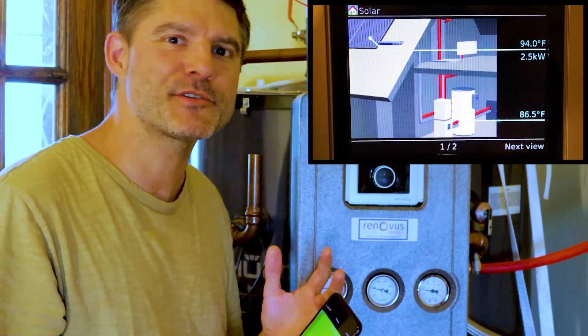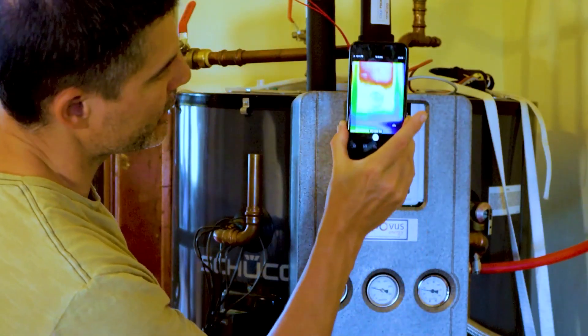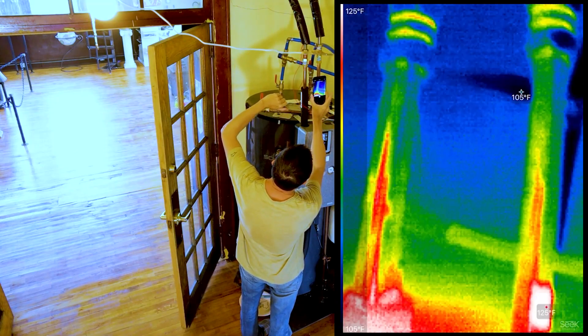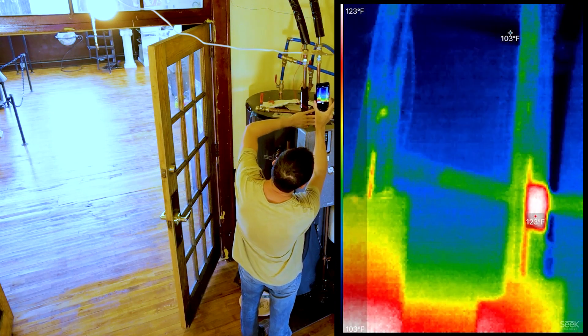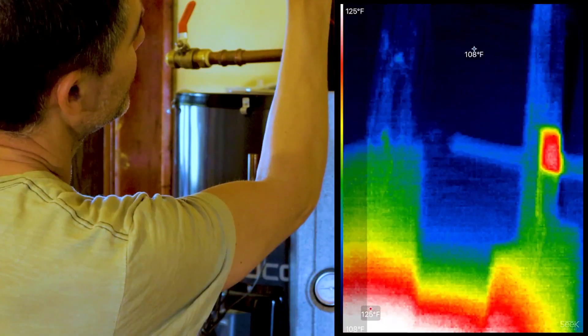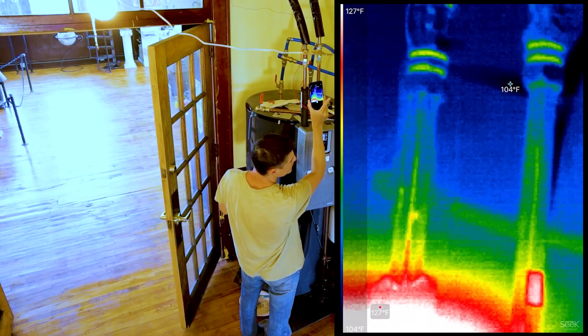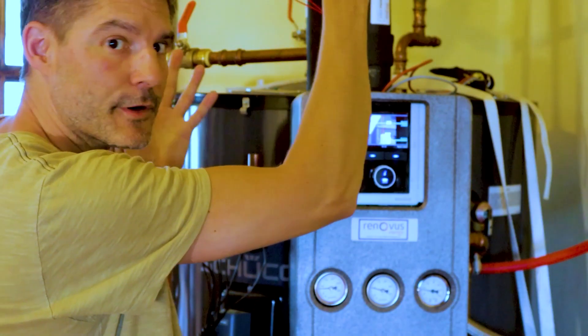Because the water temperature is greater on the roof, the circulating pump has started to run. And what's happening, if we take our infrared thermometer, is that we can see water coming from the roof that is warmer, and water coming from the water tank going back out. So it's going to start circulating and warming up the water inside the solar hot water heater until they reach equilibrium.